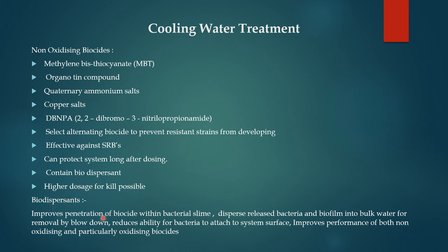Biodispersants improve penetration of biocides within bacterial biofilm, disperse released bacteria and biofilm into bulk water for removal by blowdown, and reduce the ability of bacteria to attach to system surfaces. Biodispersants improve the performance of both non-oxidizing and particularly oxidizing biocides.